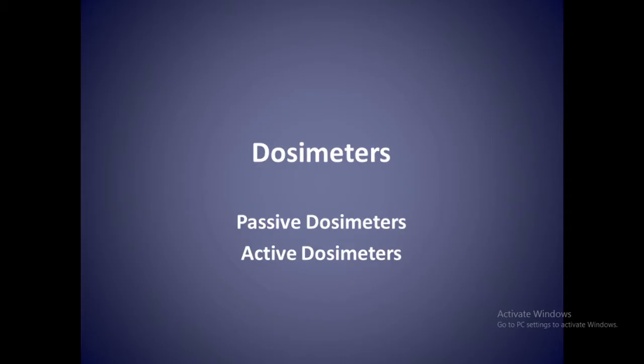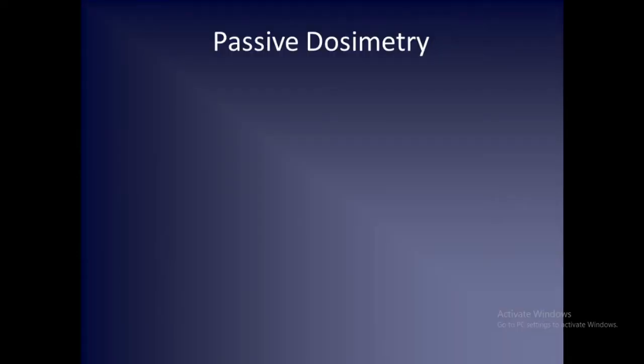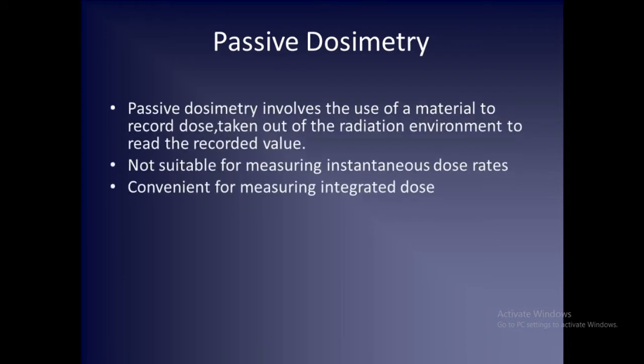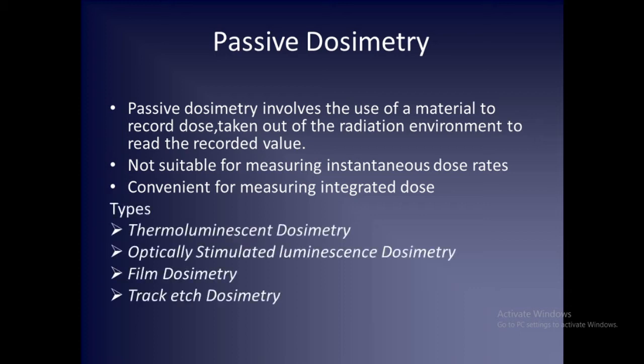Today we are going to discuss the different types of dosimeters, mainly passive dosimeters and active dosimeters. Passive dosimetry involves the use of a material to record dose and then take the material out of the radiation environment to read the recorded value. This method is not suitable for measuring instantaneous dose rates, but it is highly successful and convenient for measuring integrated dose.